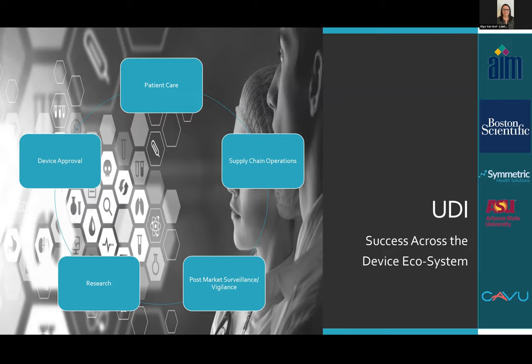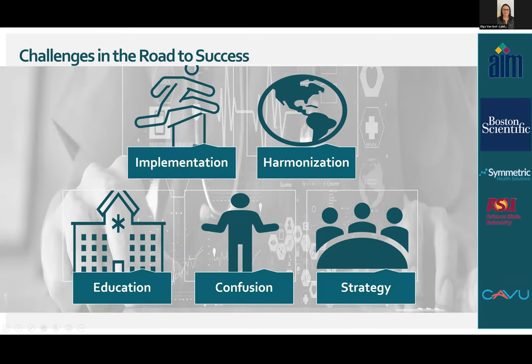My local RA counterparts have received, and continue to receive, requests from multiple hospitals in various EU member states asking us, the manufacturer, to provide them with the UDI of the class 3 implantable devices they procure from us. There's a lack of understanding that the UDI retention requirement is for the healthcare institute to record the whole UDI, including both the static UDI-DI information and the dynamic UDI PI information. It's on the healthcare institutions to capture the full UDI information on the label of the individual unit of the device with which they've been supplied, in order to keep a record of that UDI, preferably by electronic means.